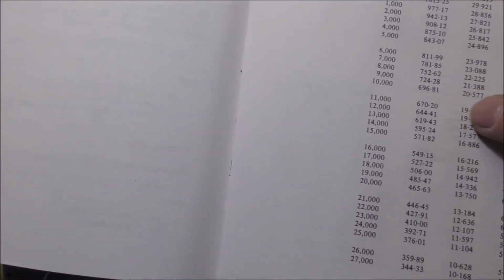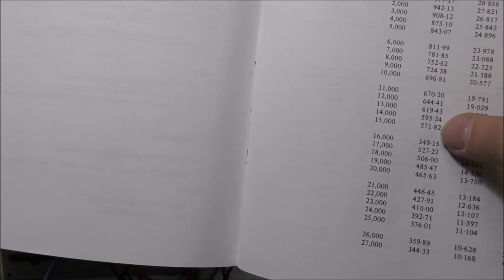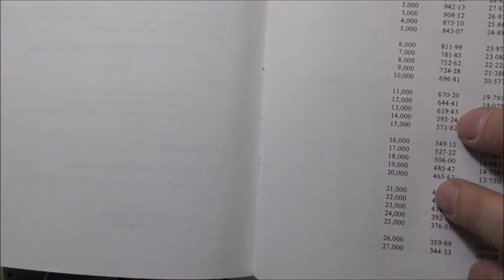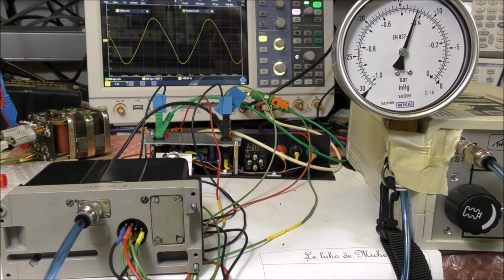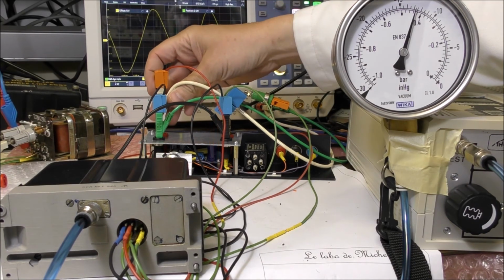We can see in this table here that for an air pressure of minus 400 millibars, this pressure corresponds to an absolute pressure of 600 millibars, which is approximately 14,000 feet. You can see that the difference between 595 and 619 here is 24, 25 millibars. So this corresponds to a change of altitude of 1000 feet. So the maximum variation of altitude which can be measured with this transducer is something like plus or minus 1000 feet. This was also the value calculated in the previous instrument, which was the Smith, I think, the sensitive Smith indicator. I will reconnect the servo control loop.